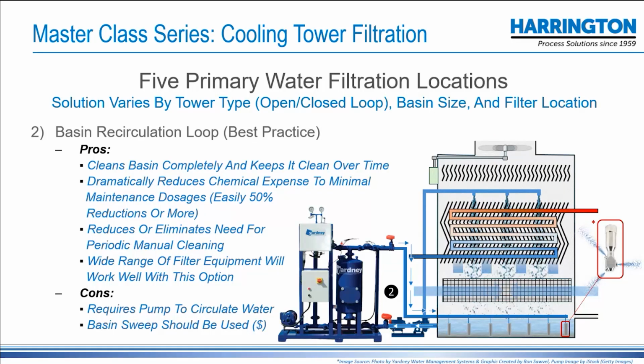Now, in that case, we used a screen filter. In the image you see here, that's a media filter. Now, if you could call them cons, you have to have a pump to recirculate the water. That's some expense. You should put in sweeps. They're very inexpensive, but it's a matter of running the pipe and nozzles within the basin itself. That will be the best solution.